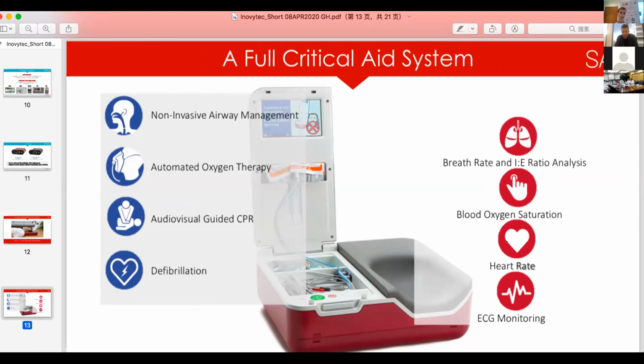The system combines defibrillation capabilities as part of the semi-automatic AED inside, audio-visual guided CPR, and automated oxygen therapy by an internal O2 cylinder, able to provide a constant and interchangeable flow of between 5 and 10 liters per minute for the patient, and also non-invasive airway management. You can see the headrest for the patient on the right side of the screen, intended to place the patient's head in a head tilt position so the airway will be open. The SALI system is intended for use by laypersons.